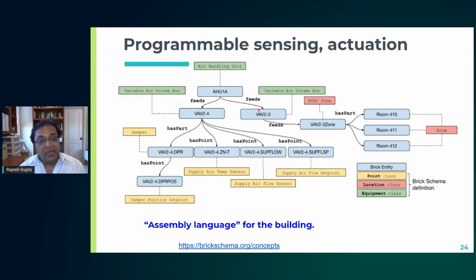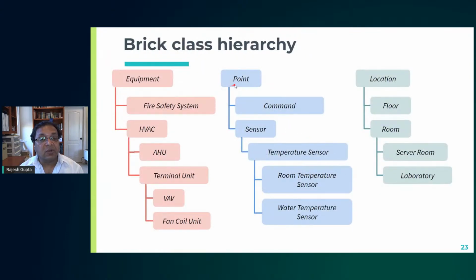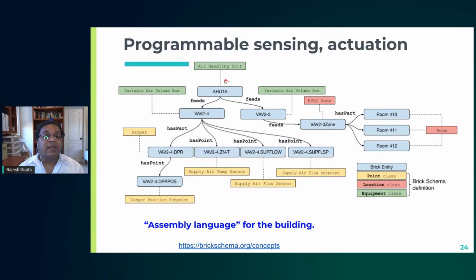So then you now have an emerging model, a graph model, if you will. So for example, in the Brick schema, you have entity, which is point, which is a class, location, which is a class, and equipment, which is a class. You have seen this: point, control point, equipment, and location. And then you have an air handling unit that feeds. So you can see the relationship. Feeds means it is physically connected through conduits to a variable air volume box, and of course it will be connected to multiple of these, and that feeds a zone which serves as a room, and multiple rooms, for example. And a variable air volume box has a part, which means it has a subcomponent, or it has a control point. Has point means control point, and so on. And these are your sensors and actuators. Okay. So now, once you define that, and there are lots of details that I'm skipping, which I think you can find on brickschema.org.